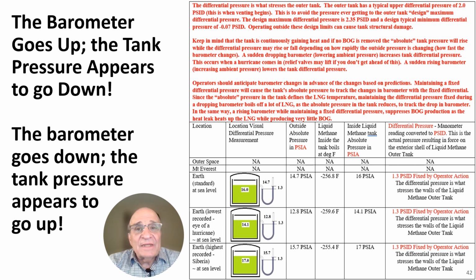Let's do the same exact thing, but now we're going to use an LNG tank. And the LNG tank we're going to see is being maintained here at 16 psi absolute with a differential pressure of 1.3 psi differential. So my barometer is 14.7. Now what I've done for this example is I'm going to maintain the differential as a constant pressure. So now if the barometer drops to 12.8, it means my absolute pressure has to drop to 14.1. And if the barometer rises to 15.7, then my absolute pressure inside the tank has to rise to 17 psi absolute.